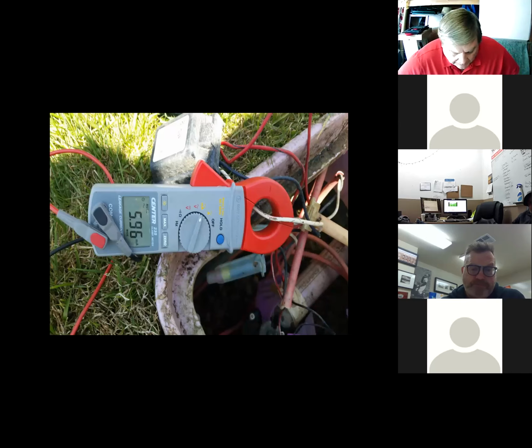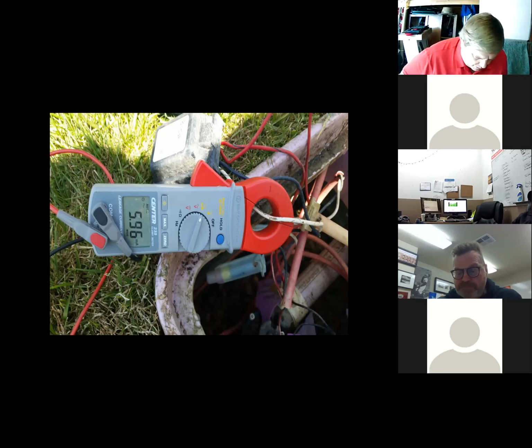Now, in looking for the bad decoder, you're doing a lot of deep knee bends because you're going to go from valve box to valve box to valve box to valve box, and you're going to grab the wires inside that valve box and clamp around individual wires. Always check each wire in the valve box and look to see, what did I start with at the clock? Each valve box, you will see a smaller current draw as you go through, looking for where the problem lies.